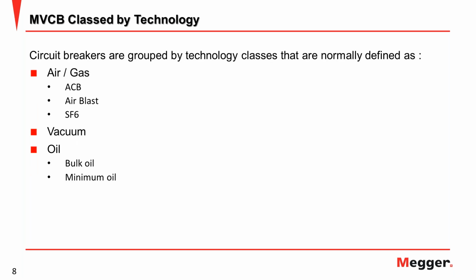Yeah, this is the circuit breaker class based on the technology. There are air or gas circuit breakers, vacuum circuit breakers, and the last one is the oil circuit breaker. For air or gas circuit breakers, there are 3 types: ACB, air blast, and SF6, using this medium to extinguish the arc when the breaker operates.